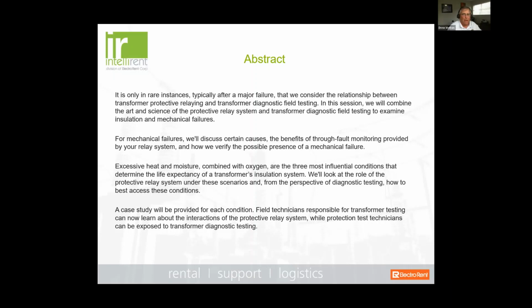So he got on site, and by the time he got on site, the maintenance team was already there putting up scaffolding, disconnecting the transformer, and getting ready to run a battery of tests on the transformer to see what possibly could have gone wrong. Well, the relay engineer approached the foreman on the job and said, "Well, wait a minute, we haven't even looked at the oscillograph or sequence of events from the relay to try and make a determination." And they kind of brushed him off and said, "Yeah, we understand. Go away. We got a lot of work to do here." As it turns out, in interrogating the oscillography, there was actually no differential current, and it was a nuisance trip from one of the protective relays. And these things do happen.